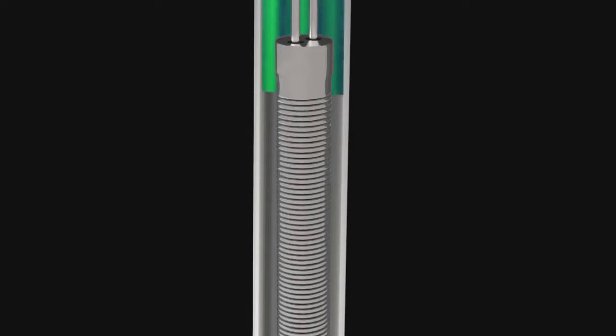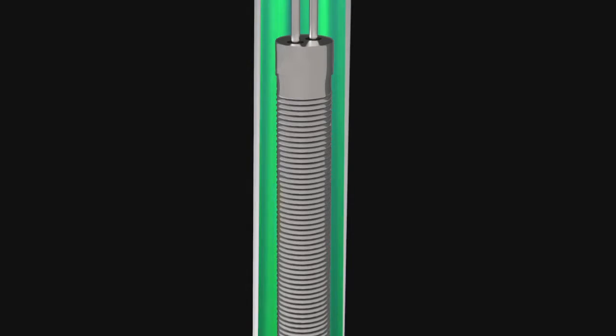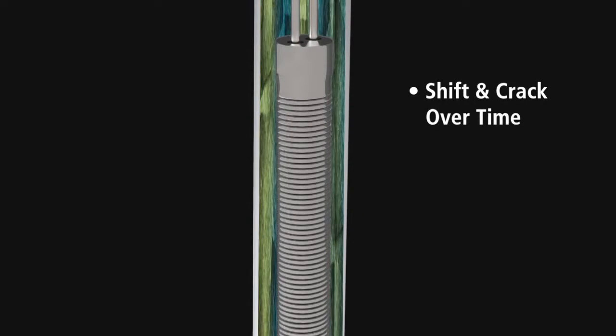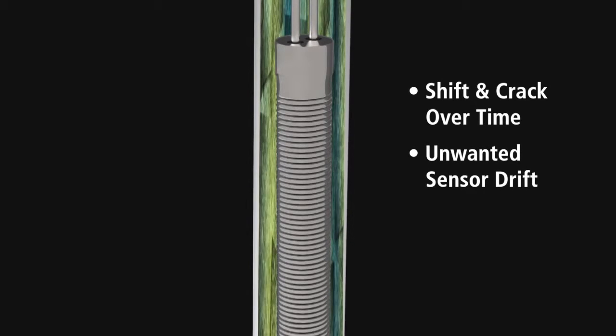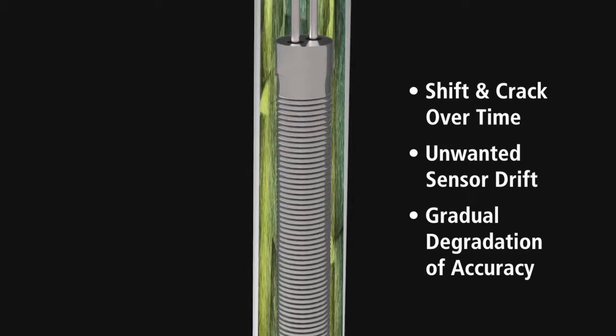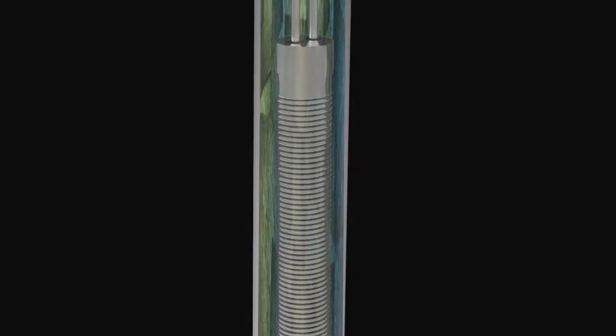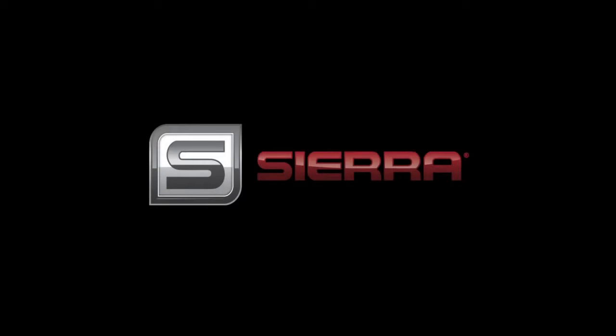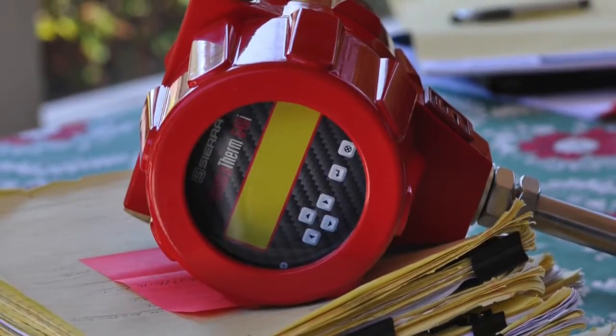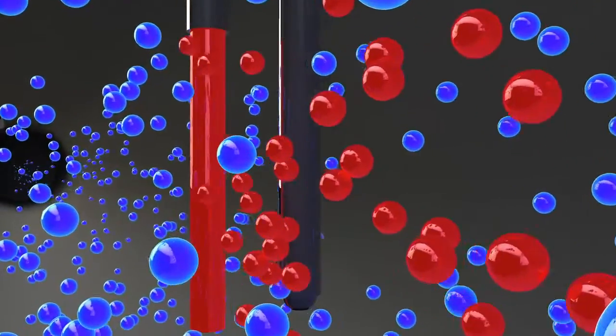To do this, he filled the air gap with a potting compound of conductive epoxy, also called thermal grease or cement. This type of sensor is known today as a wet sensor. This wet design proved that it did work, but had its weaknesses. Wet thermal sensor design, because of the organic potting cement used, would shift and crack over time, causing unwanted sensor drift, resulting in a gradual degradation of flow measurement accuracy. Today, wet thermal sensors are used by all industrial thermal sensor manufacturers on the market, with one exception, and that is Sierra. Sierra never stopped improving the technology, knowing that wet sensor drift problems must be solved.